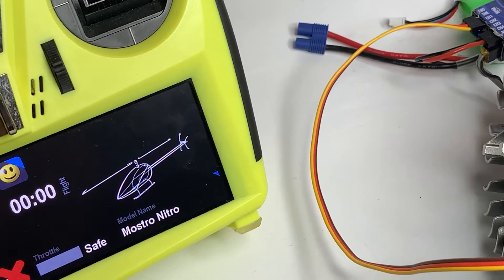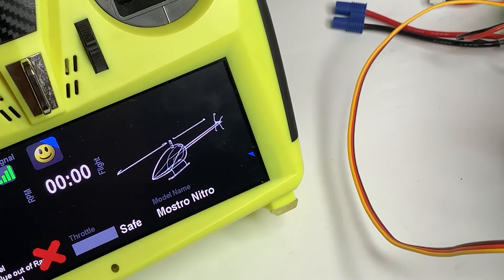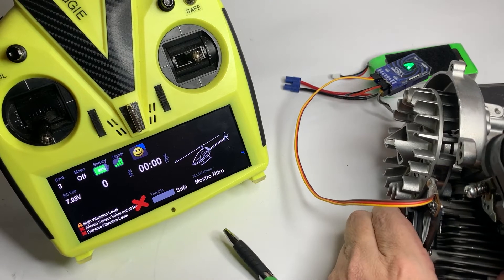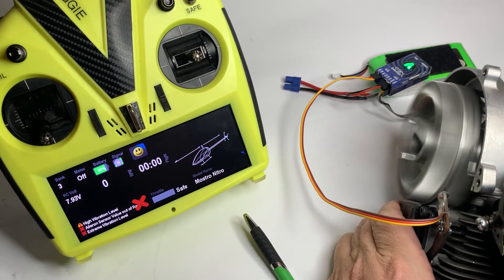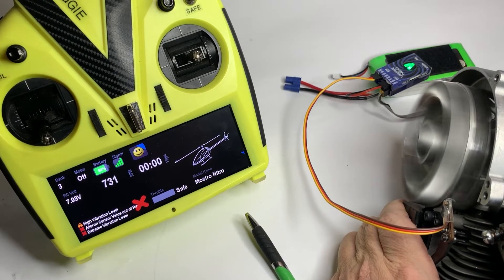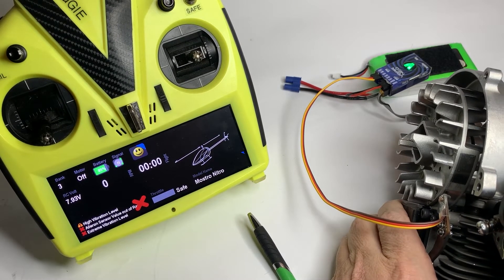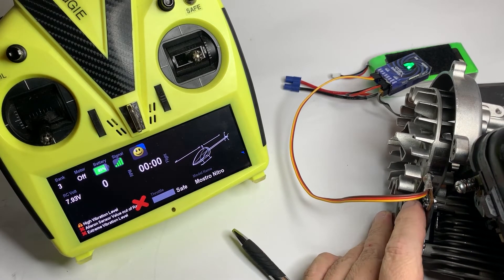And by doing that, you will see that immediately we get perfect readings. I attached a drill so we can spin it — 800 RPM or something like that. So now it has a good signal. And that is all you need to do — just move it like that.